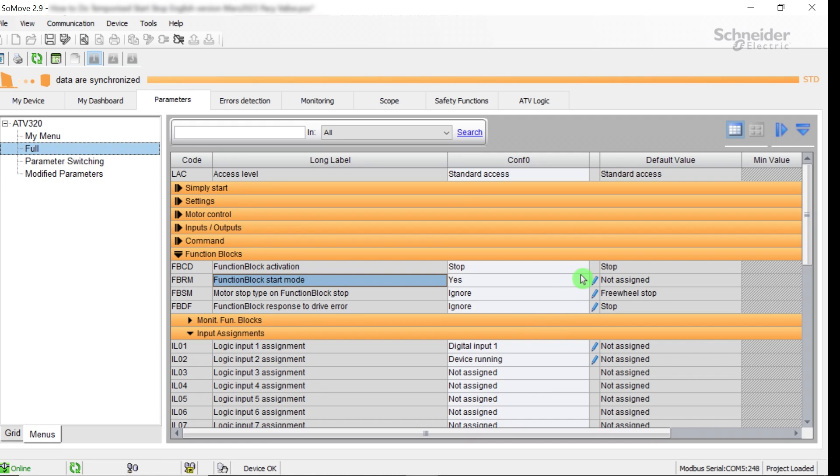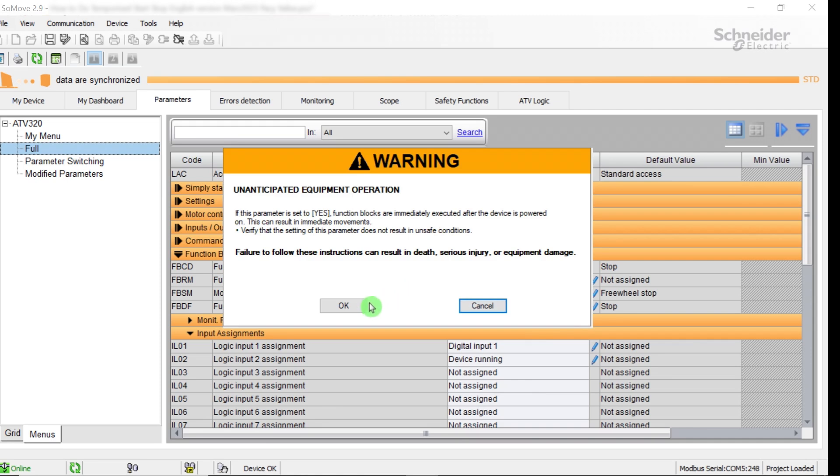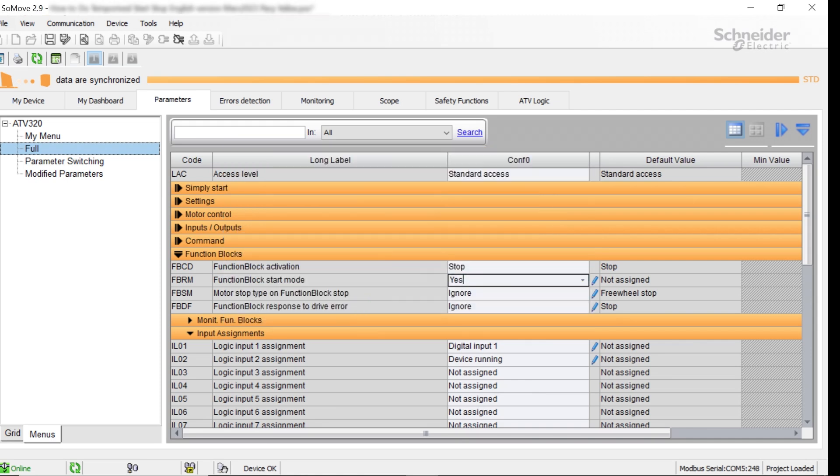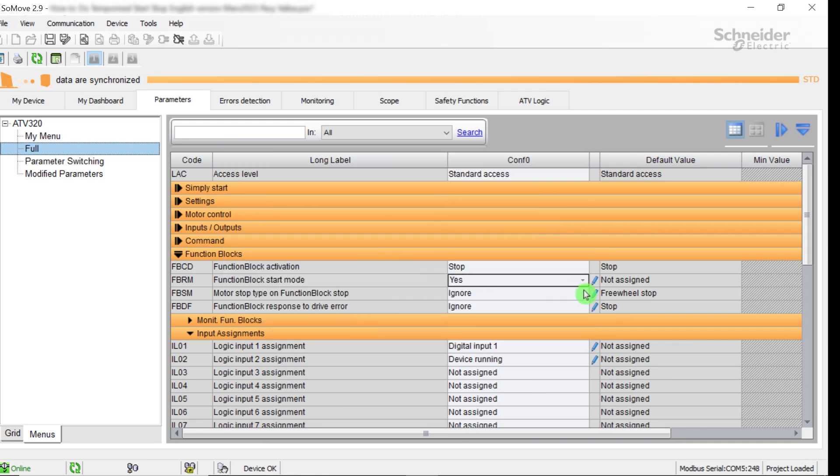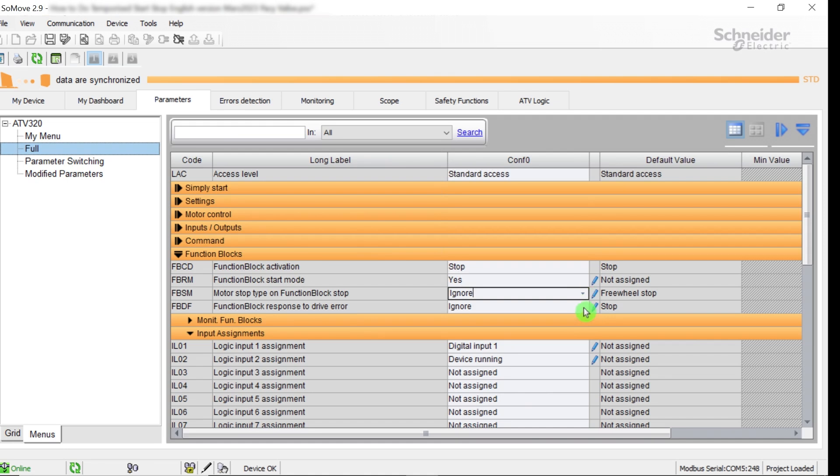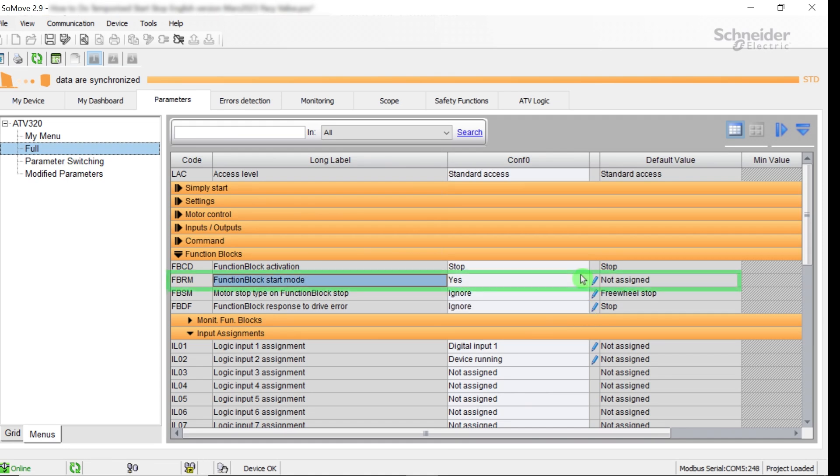The ATV logic tasks may be running automatically at ATV320 startup if function block start mode FBRM is set to Yes. If function block start mode FBRM is assigned to a logic input DI1, DI2, it will execute or stop the ATV logic program.